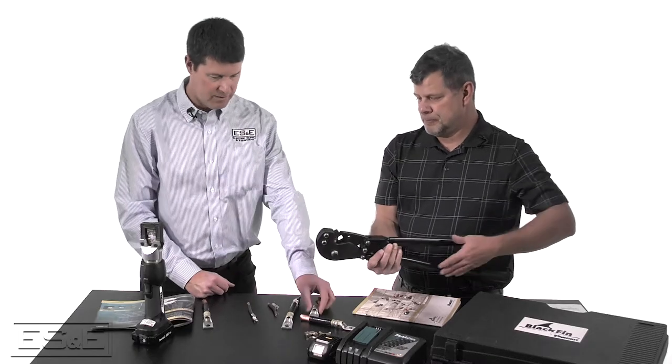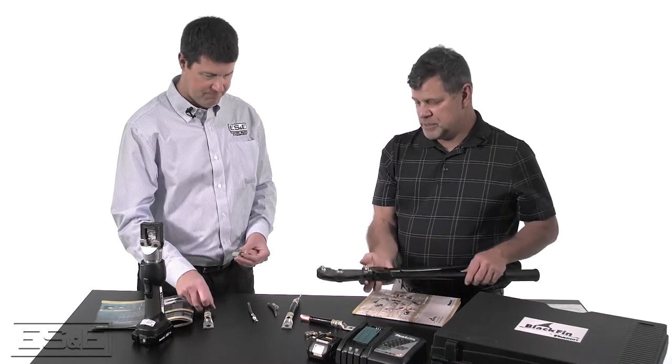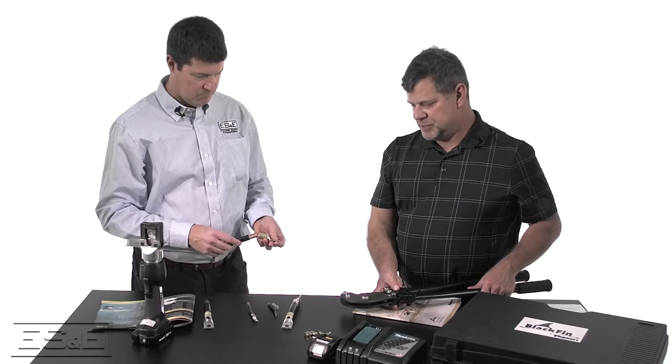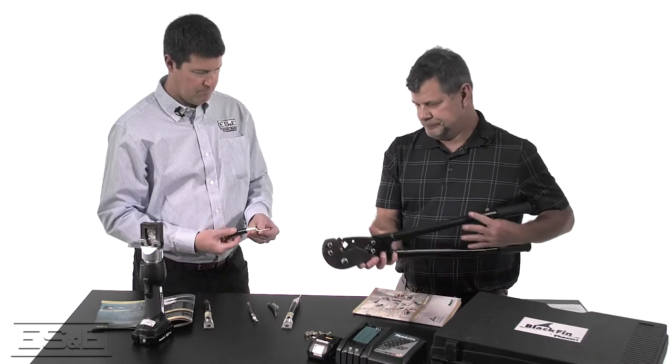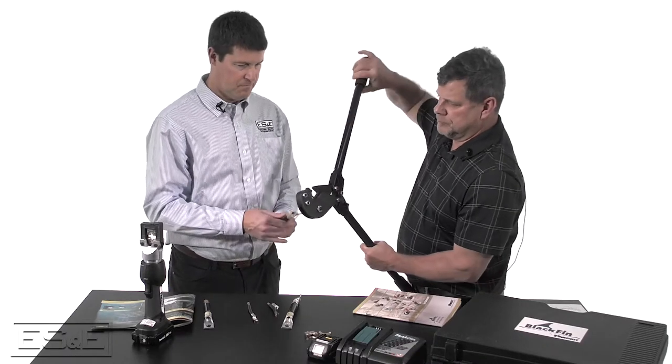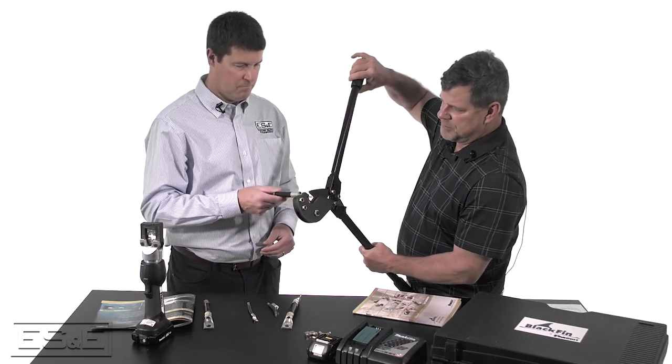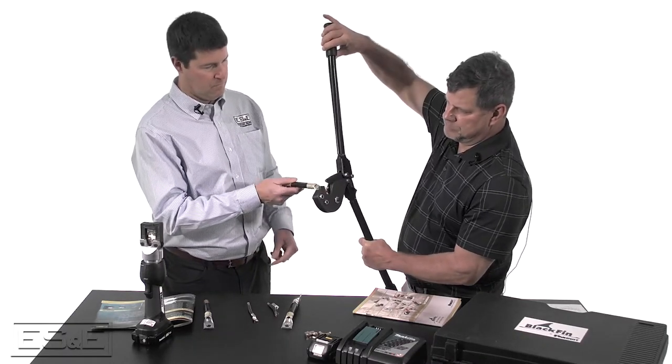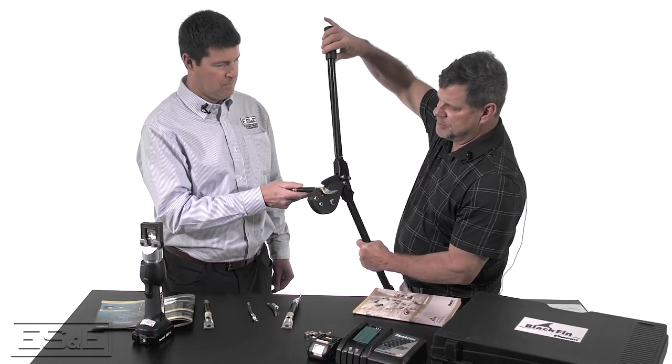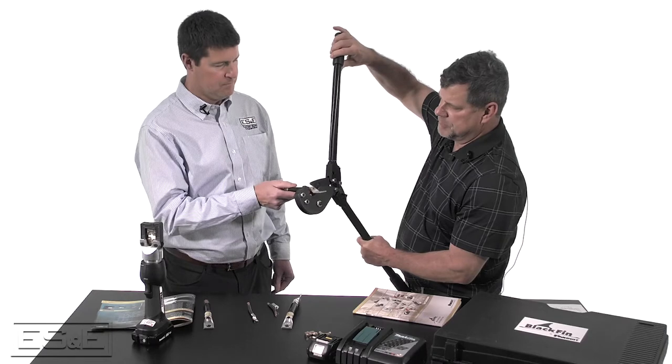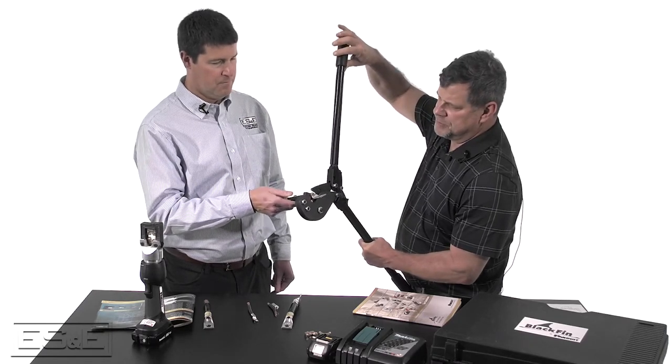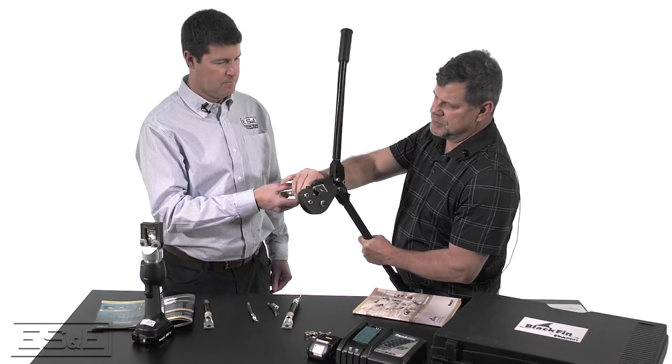You want to show us how to do a crimp with it? Yeah, let's go ahead and do it. We've got it set up right now to do a 250 MCM. If you want to go ahead and place that in there. And place it at the, there you go. And actually, let's rotate it 90 degrees. Let's do it right there.